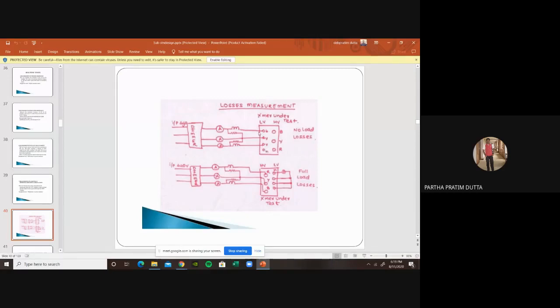We apply the rated voltage to the LV side and keep the HV side open. So the entire no load loss test happens, and through our meter, the 2-watt meter method, or our power analyzer. Previously we used the 2-watt meter method, but right now we are using the power analyzer, and we come to know what the no load loss is.